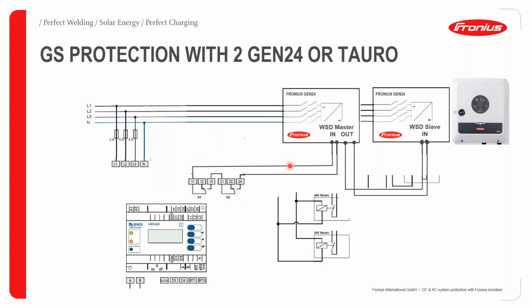So before that, let's now see how this can be implemented using, let's say, multiple Gen24 or a mixture of Gen24 and a Tauro. So in this case, all that needs to be done is to have them connected respectively to the WSD terminal, but then please ensure that only the first inverter is in the master position. We're going to see that much more clearly in the subsequent slide. Whilst for the other inverters, the WSD mode is in the off position or in the slave position.